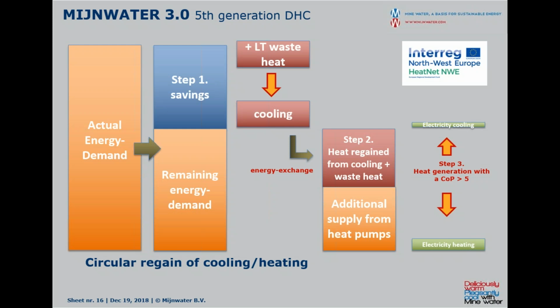And we add up low temperature waste heat. So by keeping the return flow from the cooling and the waste heat, we can reduce the energy amount back to about 35%. In fact, let's say it's 50%. So we have a 50% energy reduction for buildings in the city just by building this kind of district heating and cooling grid. And then we have the very strong heat pump operating at a COP of 5.